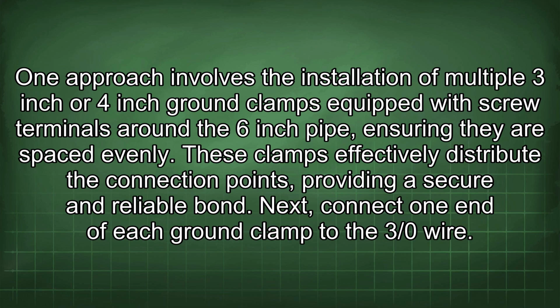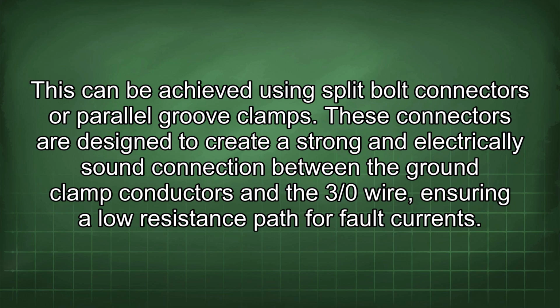One approach involves the installation of multiple 3-inch or 4-inch ground clamps equipped with screw terminals around the 6-inch pipe, ensuring they are spaced evenly. These clamps effectively distribute the connection points, providing a secure and reliable bond. Next, connect one end of each ground clamp to the 3/0 wire. This can be achieved using split bolt connectors or parallel groove clamps.